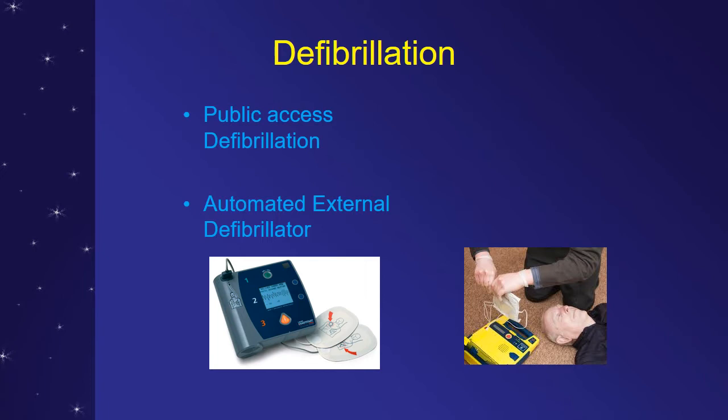If it is a shockable rhythm, whether this is a VF or VT, that is detected by the machine, and that will give a verbal prompting. So the speaker of this machine would say, okay, so the sensors are in the pads. So pads are used for sensing the rhythm and for delivering the shock, for both.